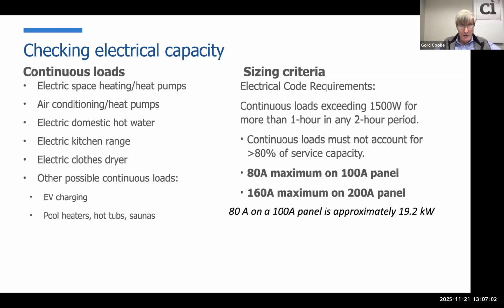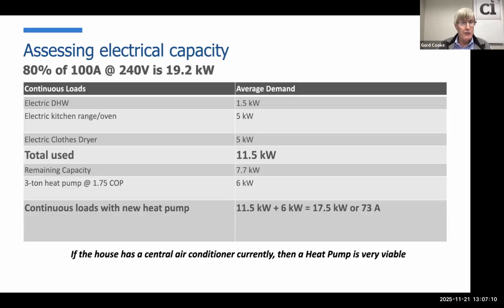So you go, what can I do with 80 amps? Well, I certainly can't put electric baseboard heating in an old house on 80 amps. But if we look at a typical house, domestic range, electric kitchen, electric clothes dryer, if we look at that total amount used, 11.5 kilowatts, so what do we have remaining? We have the ability for 7.7 kilowatts. And if a 3-ton heat pump at 1.75 COP uses 6 kilowatts on that very cold day, we can do that. We have enough room in that 100 amp panel because I have available to me about 19 kilowatts. So if we are accurate in our sizing and we're accurate in our understanding of how a low load house works, then in fact, we may not need to upgrade the panel.